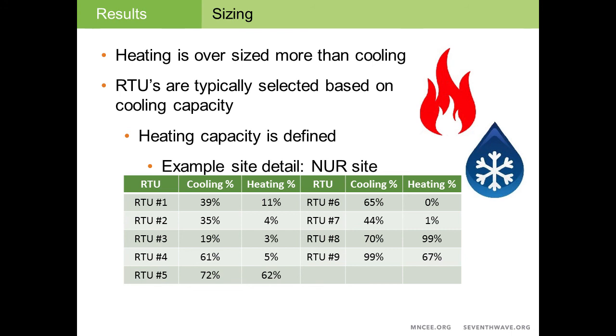And as an example, I show you some heating and cooling percent of capacity for one site. And you see that there are areas that have pretty close to capacity, referencing rooftop unit 8 and rooftop unit number 9. But those were exterior zones that had south-facing facades that had a lot of external heating and cooling requirements, whereas rooftop units 1, 2, and 3 had interior zones and didn't have a lot of heating requirements.